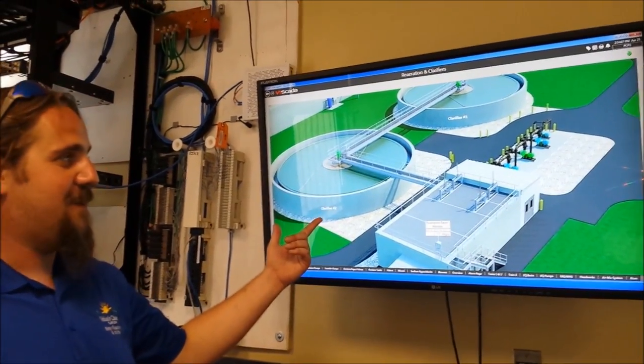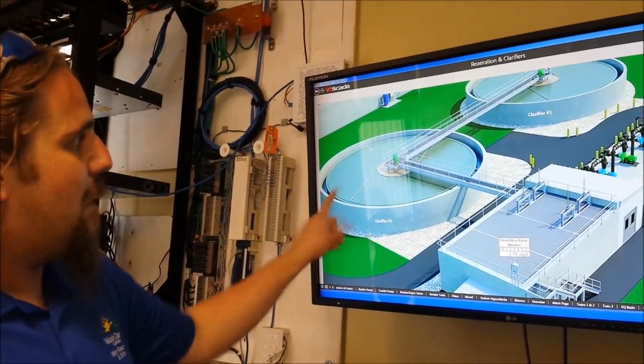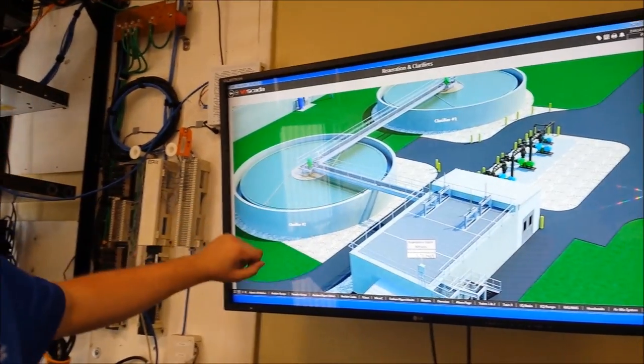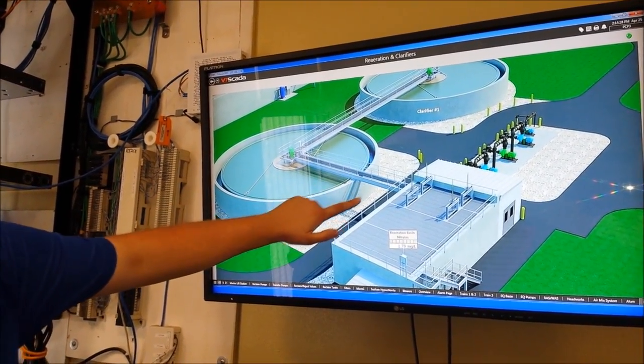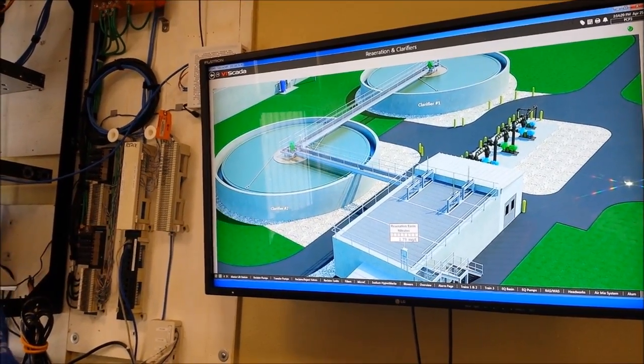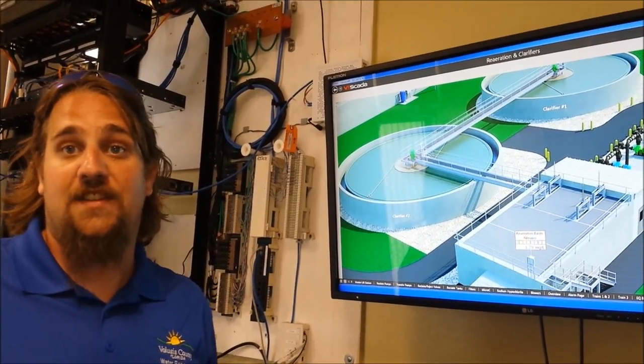So here we have the clarifiers. Everything that has been treated in the Bardenpho zones ends up coming right here. And the sludge blankets actually settle in these circular tanks in the very bottom. And we actually monitor how deep the sludge blankets are, and that indicates how effective our process is running.